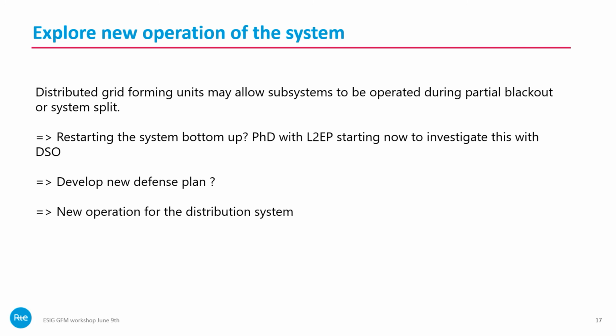We can also try to develop new defense plans. For example, in France we have specific defense plans where, in case of loss of synchronism or a very stressed situation, we can split the system into subsystems to avoid the spread of the issue. With grid forming, we can again rethink this defense plan. And as I mentioned, we definitely need to think about new operation of the distribution system.